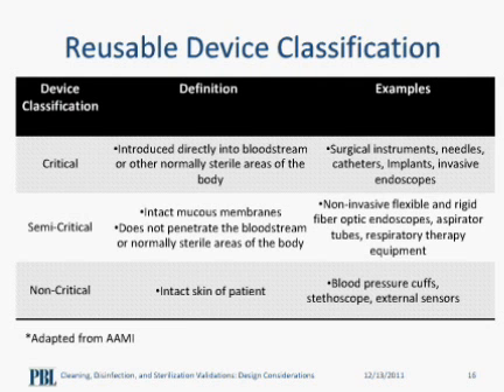Now that we have gone over the procedure, we have to figure out which end process we should use for our device. Will the device's reprocessing procedure end at the cleaning level, disinfection, or sterilization? We distinguish that by classifying our reusable medical device.